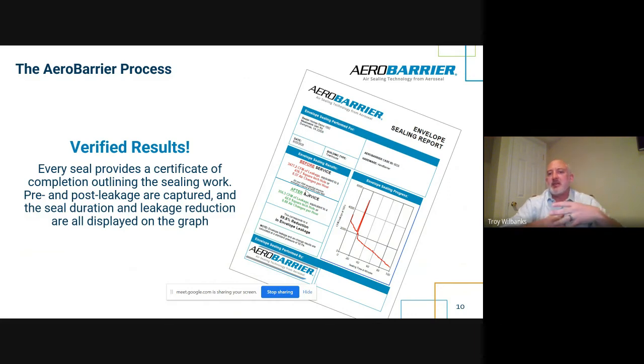So in this example, it was a townhouse. It took it from almost 3,500 CFM of leakage down to 356. If you added up all those leak points before the service, they would add up to about a 418 square inch hole. After service, it was 42 square inches. Air changes per hour went from 8.57 to 0.88. We did that in about an hour and a half. I don't know a trade or a technology out there that can really do that.